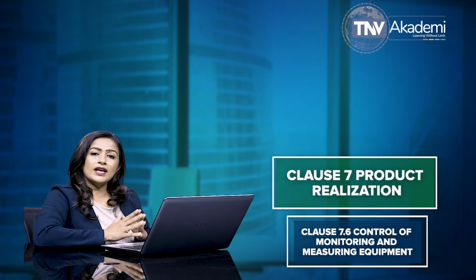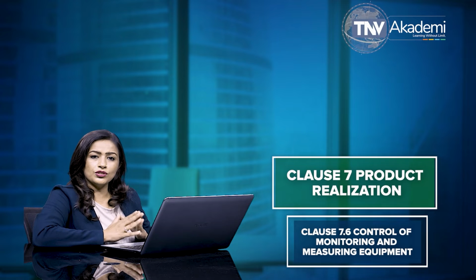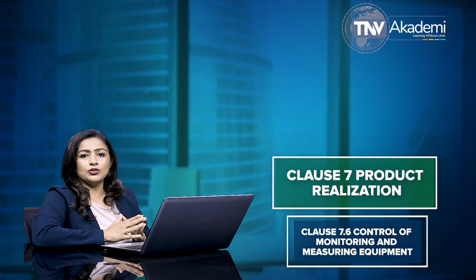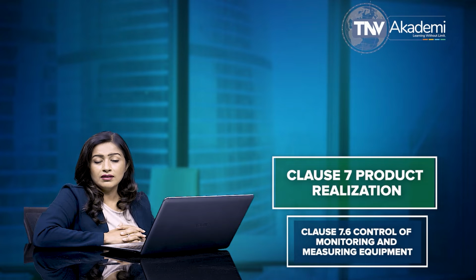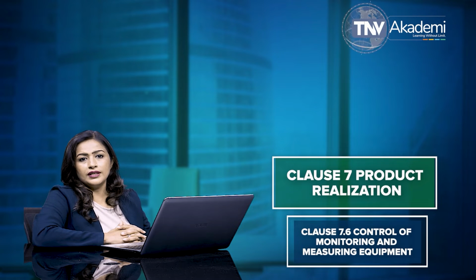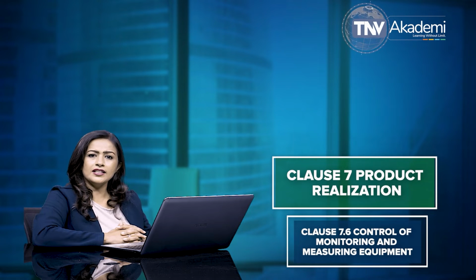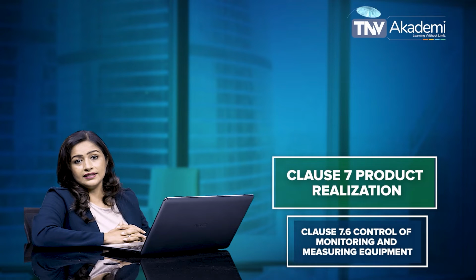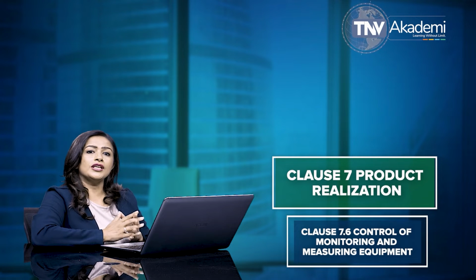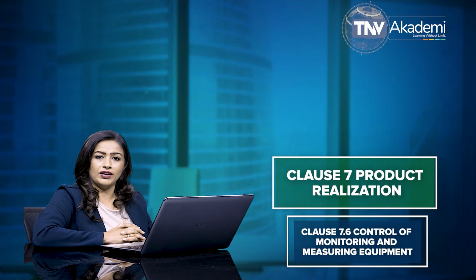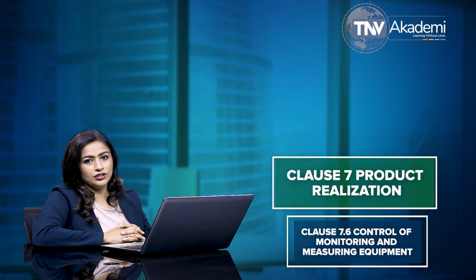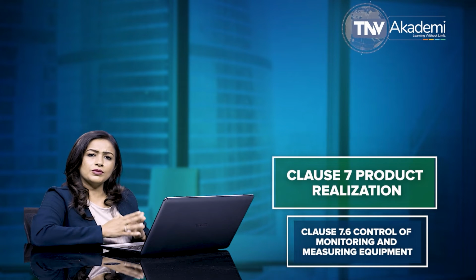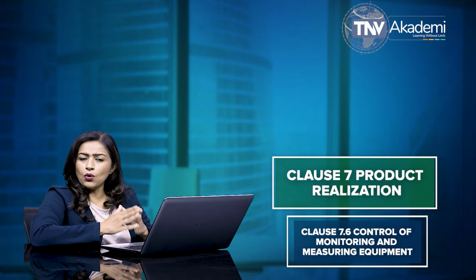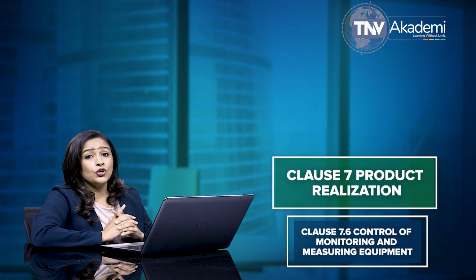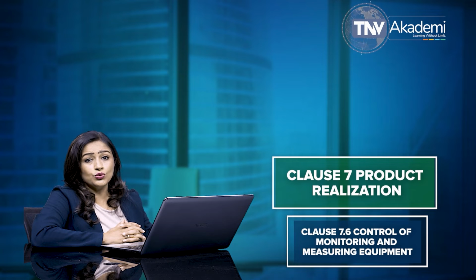The clause says that the organization is required to document procedures to ensure that monitoring and measurement can be carried out in a manner that is consistent with the monitoring and measurement requirements. As per subclause 7.6, as necessary to ensure valid results, measuring equipment must be calibrated or verified, or both, at specified intervals or prior to use against measurement standards traceable to international or national measurement standards. When no such standards exist, the basis used for calibration or verification shall be recorded.